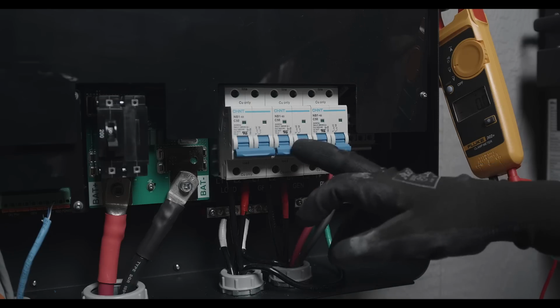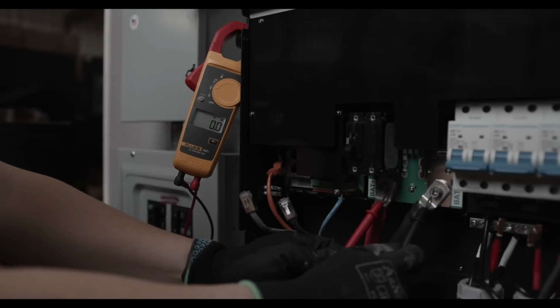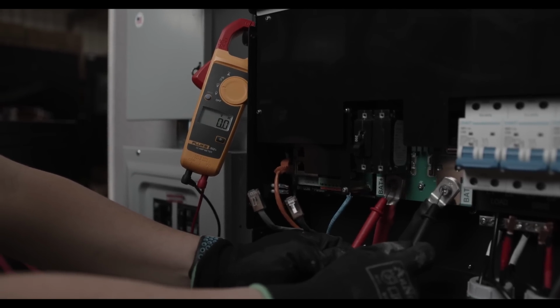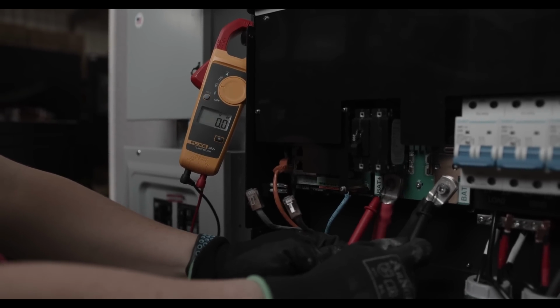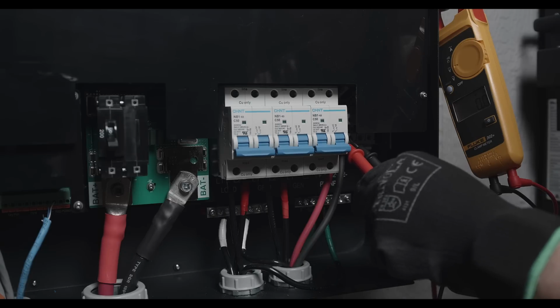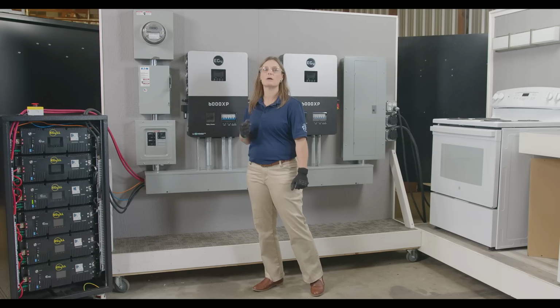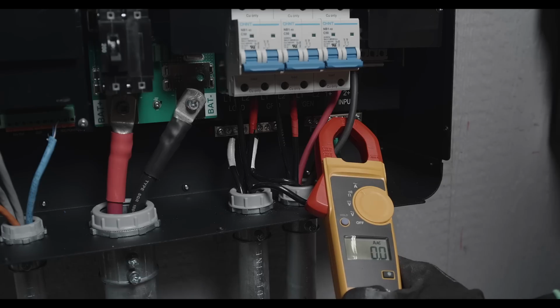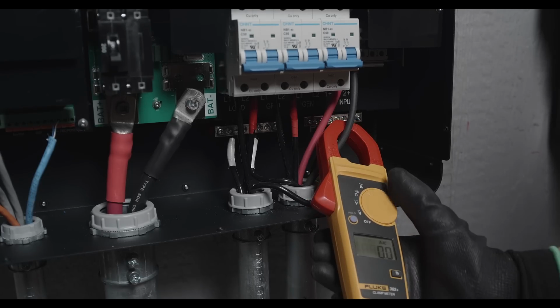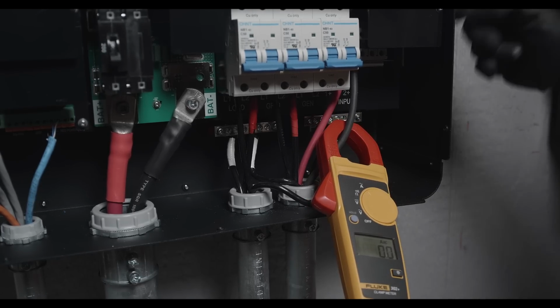Ensure all circuit breakers are in the off position. Using a multimeter, check the battery bank to ensure no DC voltage is present. Check the external PV isolator switch via multimeter to ensure the DC voltage is in the MPPT's optimal operating range, 100 to 480 volt DC and less than 17 amps, as well as less than 4,000 watts per MPPT.